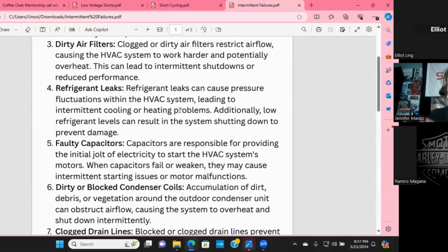It can be the first thing you do when you get there, regardless of what the problem is. And if that's the first thing you do, then the whole time you're there, you know that that is not the problem. Always replace with one that is the correct MERV rating so that you're not adding restriction to this static pressure. And then low refrigerant levels and refrigerant leaks.